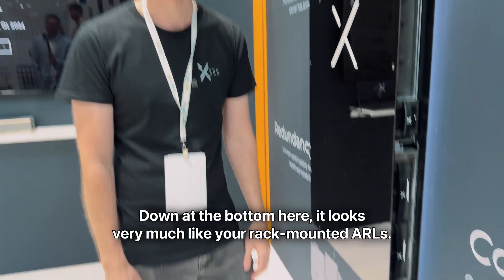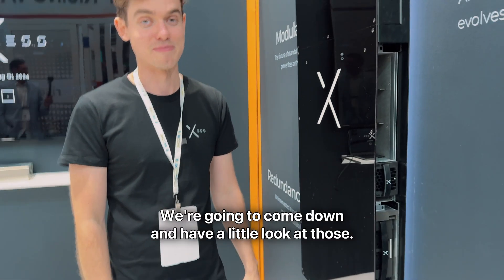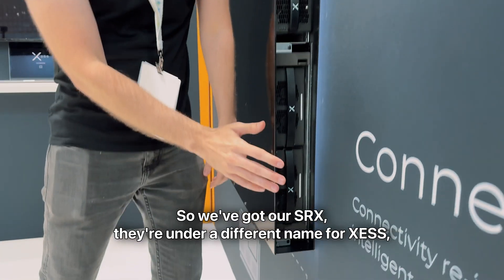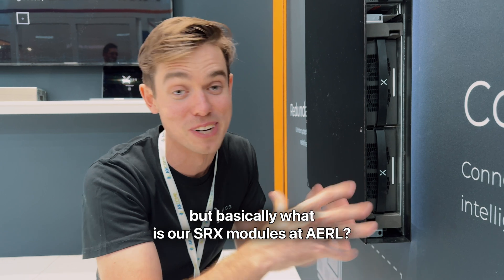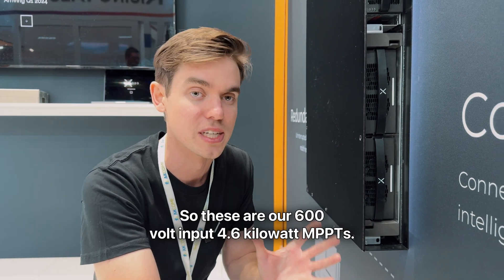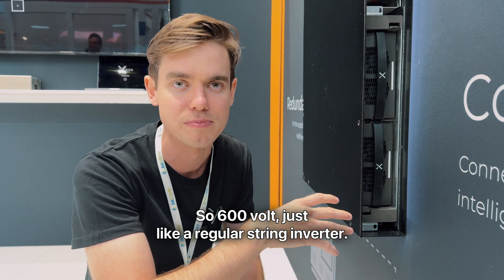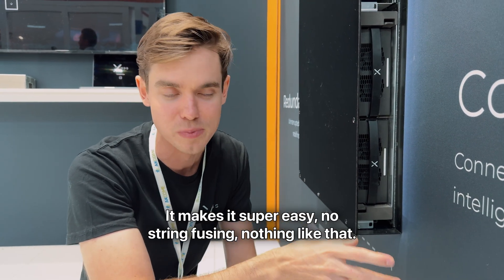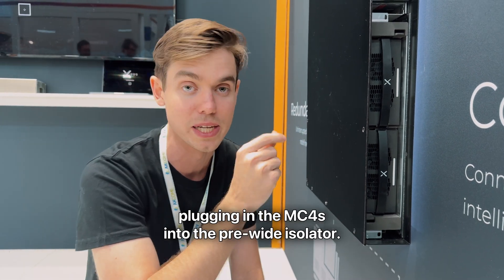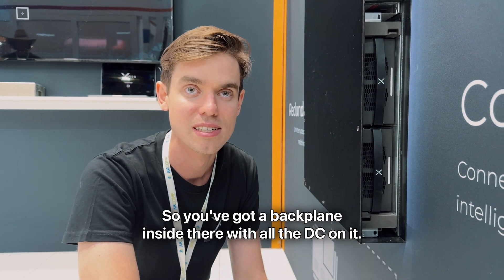Let's go from bottom to top. Down the bottom here, it looks very much like your rack-mounted AERLs. We've got our SRX modules — they're under a different name for XESS, but basically what are our SRX modules at AERL? These are our 600-volt input, 4.6-kilowatt MPPTs — single-string MPPTs, just like a regular string inverter. It makes it super easy: no string fusing, nothing like that. Up the top section you're just plugging in MC4s into the pre-wired isolators. There's a backplane inside with all the DC on it.